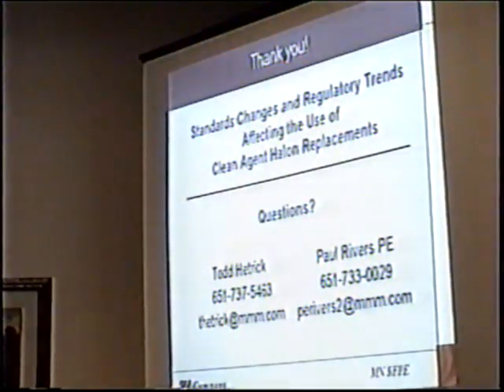You might be able to use some of the piping as a system for any of these agents. There's one system that uses a bank of nitrogen bottles that push the agent in what's called a piston flow arrangement. Fenwal has that, and they are able to use the existing piping, change the nozzles, and put a different special nozzle on it. Chubb Systems has a 500 PSI system that can use the existing piping in certain scenarios. But for the most part, you're not going to be able to drop in another agent to replace it.